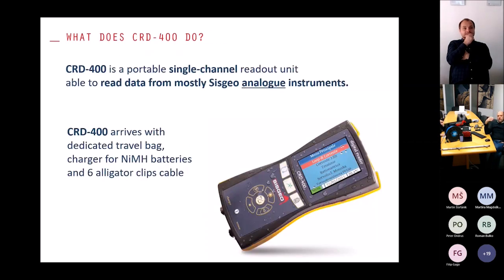CRD 400 is a single channel readout able to read analog Sisgeo instruments. It can read vibrating wire sensors, 4 to 20 milliamp sensors, and millivolt sensors, but it is not able to read all the new digital sensors. I want to underline this: CRD 400 is not able to read digital sensors.